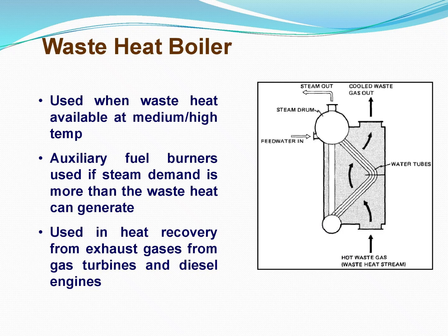Waste heat boiler. Used when waste heat is available at medium or high temperature. Auxiliary fuel burners are used if steam demand is more than the waste heat can generate. Used in heat recovery from exhaust gases from gas turbines and diesel engines.